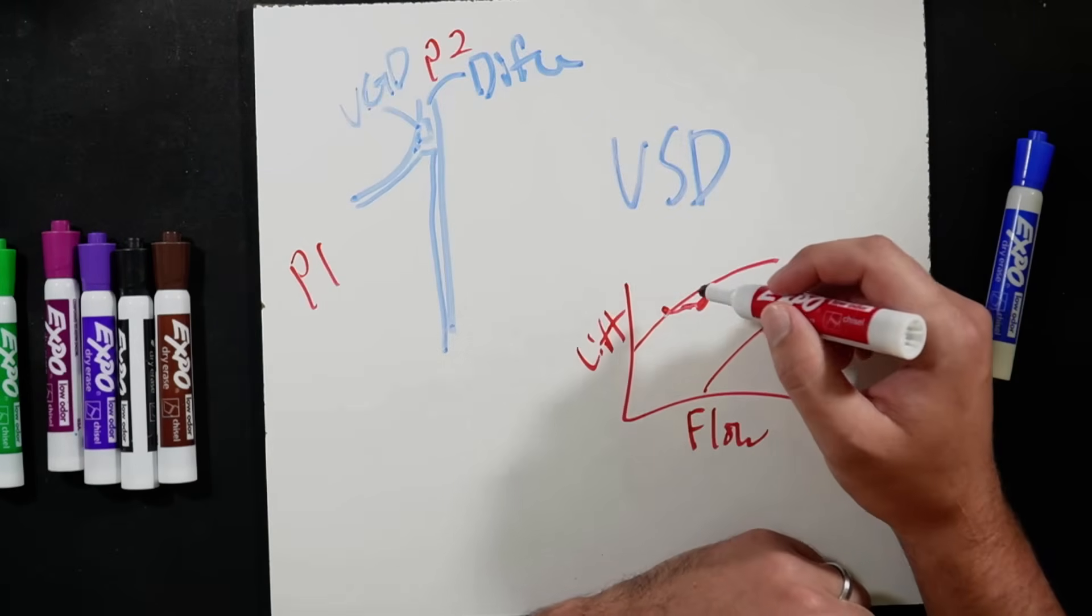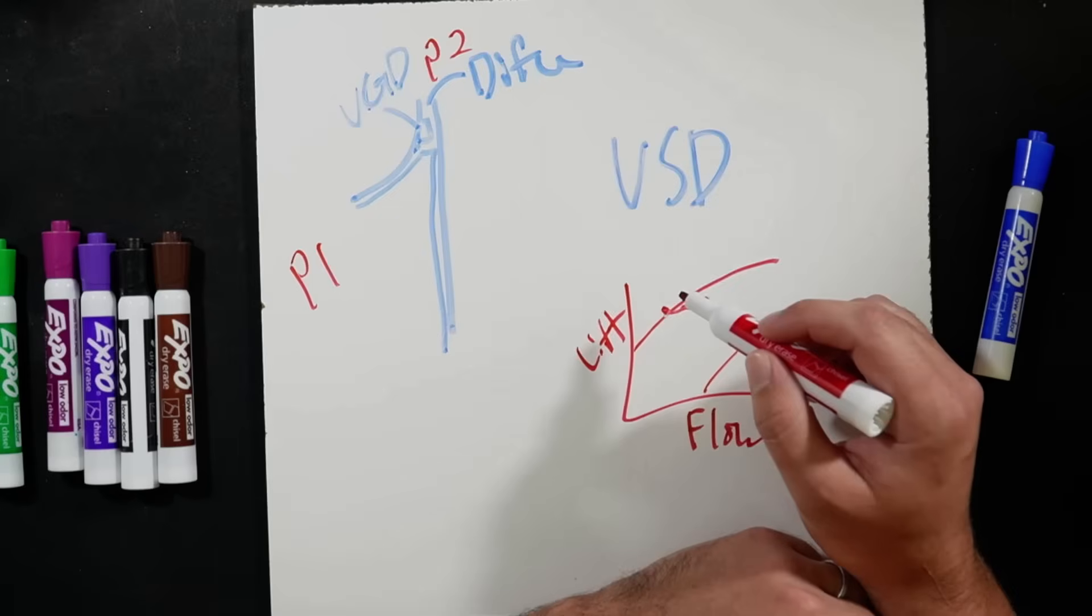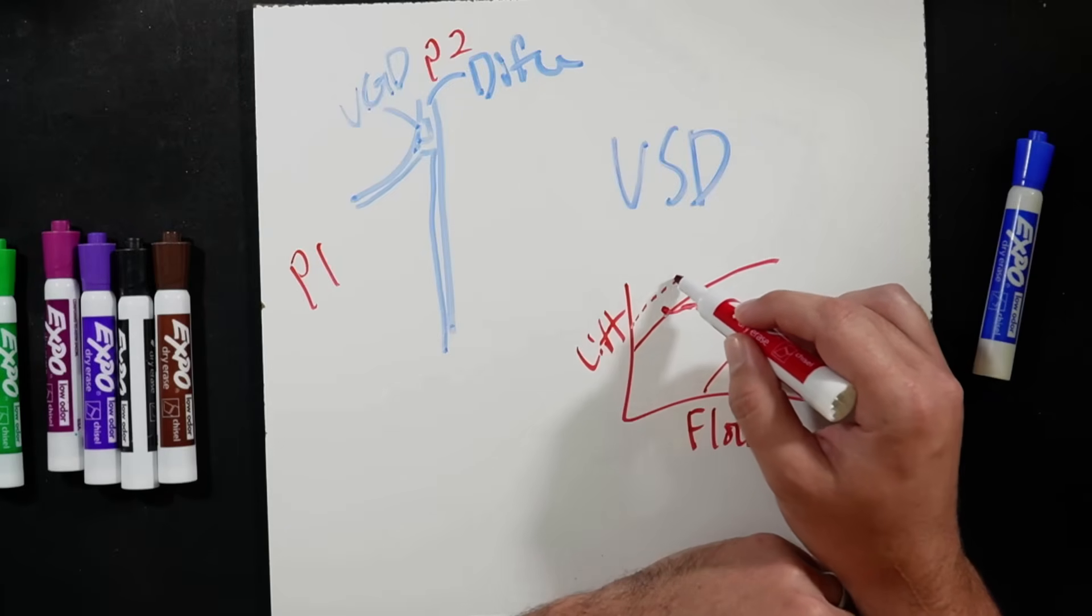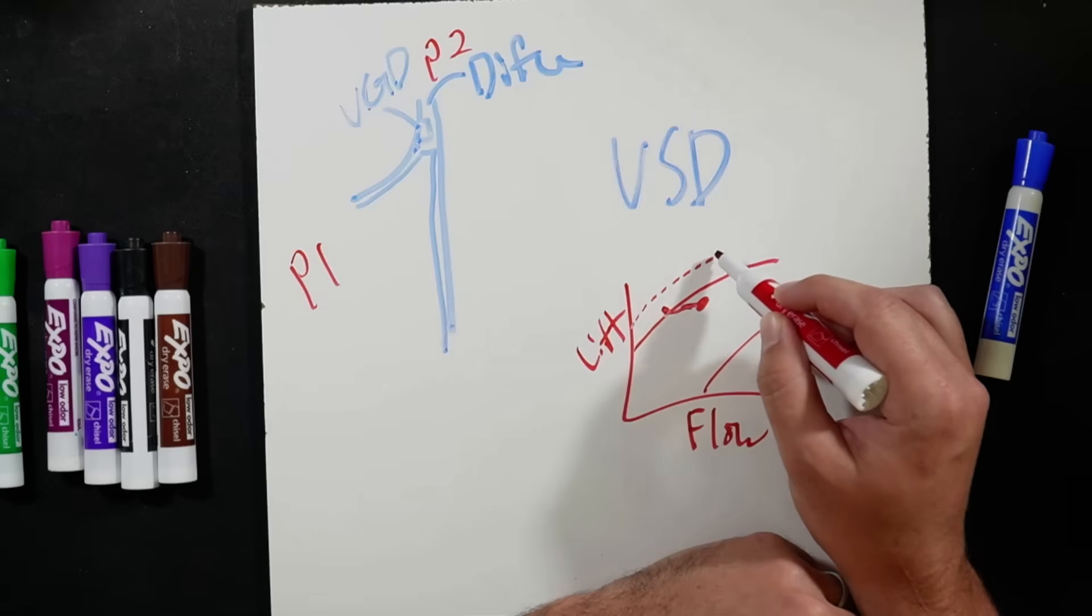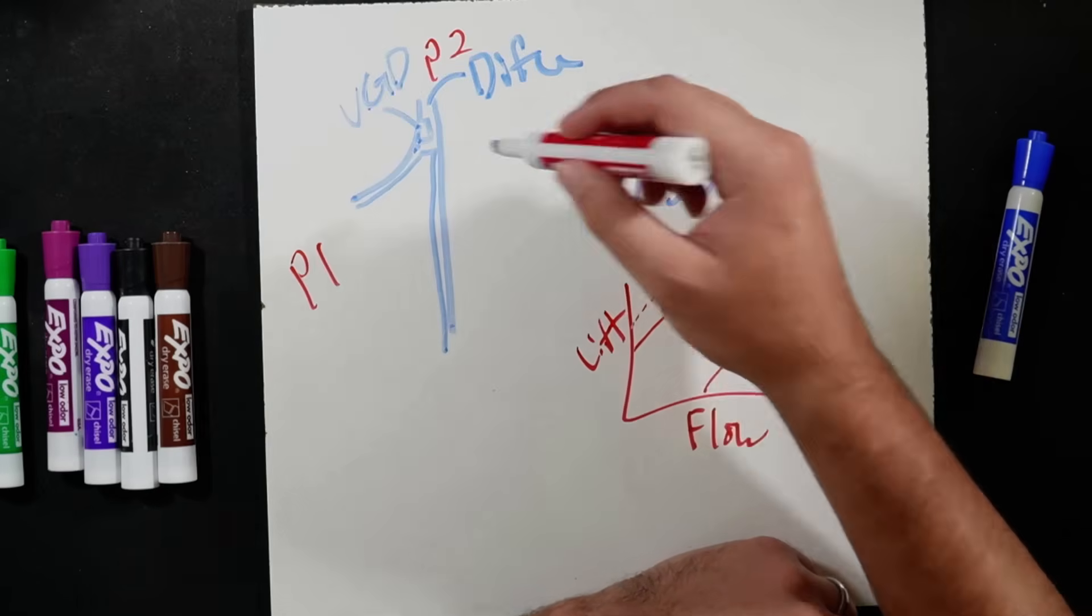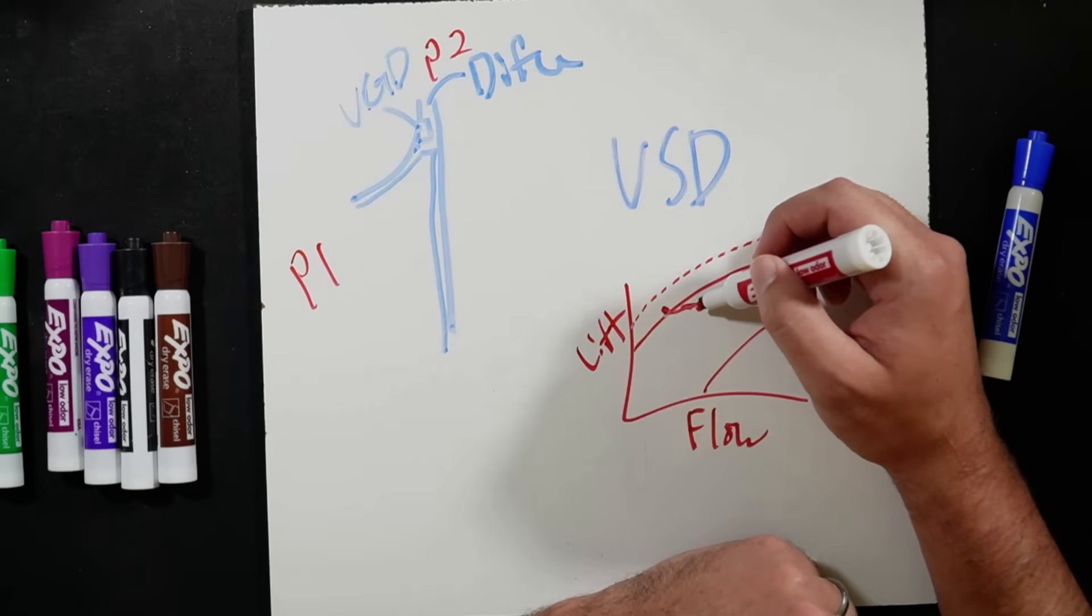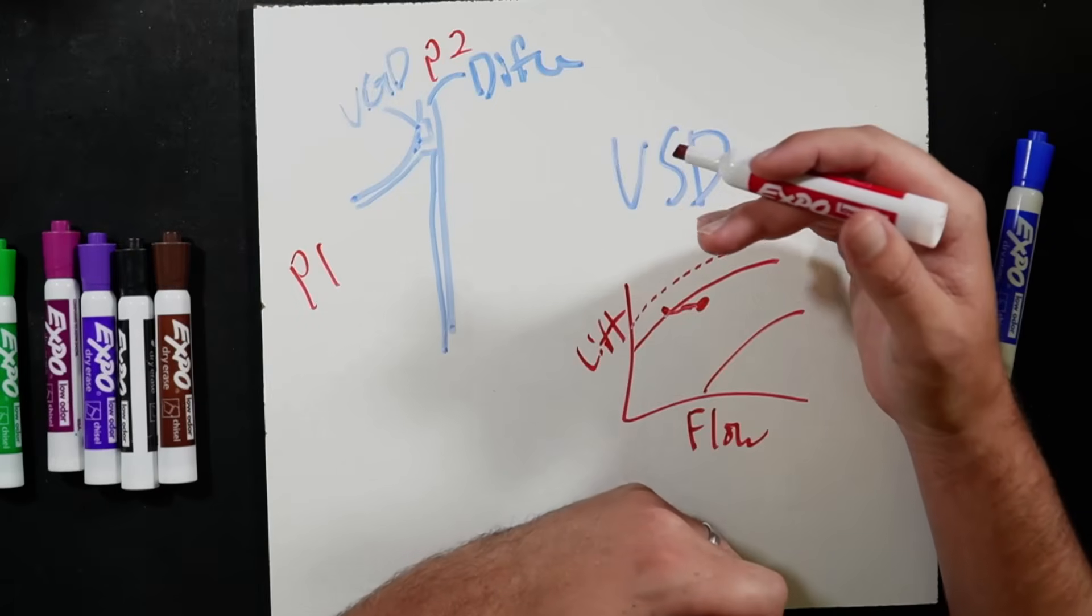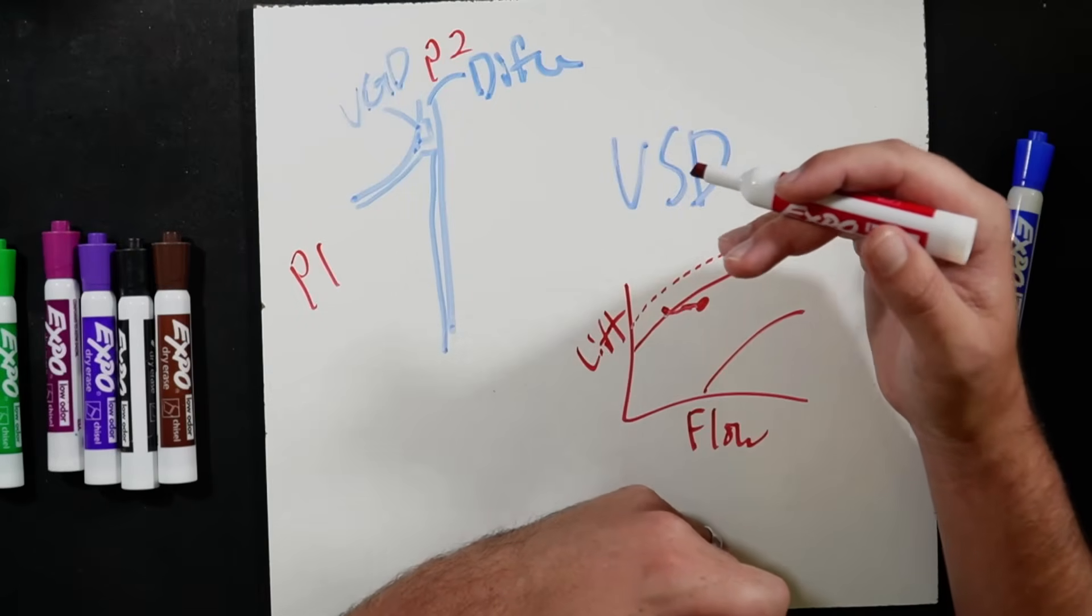Where this VGD, part of what it does, the best way I could try to describe it on this graph would be it can adjust how much lift we can handle. So just imagine that with this VGD, by using it, we're going to be able to handle a higher lift without going into a stall or a surge condition.